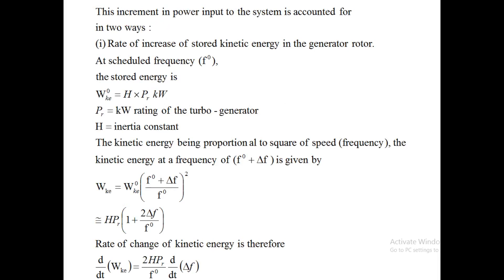This increment in power input to the system is accounted for in two ways. One is the rate of increase of stored kinetic energy in the generator rotor. At a scheduled frequency f_0, the stored kinetic energy can be represented as H * P_r, where P_r is the kilowatt rating of the turbo-generator and H is the inertia constant — kinetic energy stored divided by the rating of the machine. So kinetic energy stored equals H * P_r.